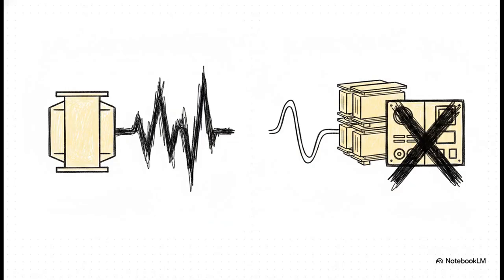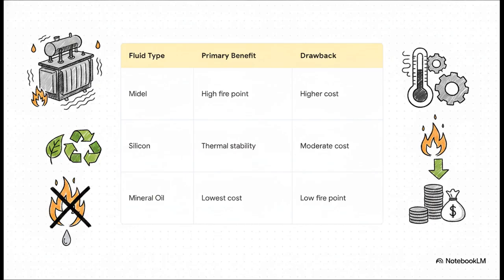And the real-world impact of this proportional scaling is massive. By adding more phase-shifted secondaries, you actively cancel more harmonic orders. When you upgrade from a 6-pulse system, which has heavy aggressive distortion, all the way up to a 24-pulse system with 4 phase-shifted secondaries, you drastically reduce the distortion on your rig's network. You're getting the cleanest possible current draw, which means you minimize the need for heavy, super expensive harmonic filtering equipment downstream. All right. Let's move to the second design axis, the insulation liquid itself.